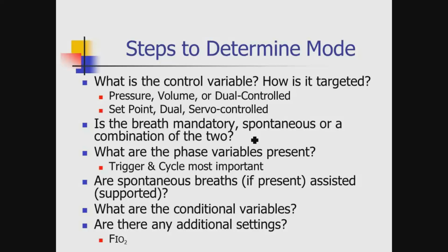Is the breath that is being delivered a mandatory breath, or does it have the ability to have spontaneous breath, or a combination of the two? Each mode is going to be a little bit different as far as whether or not they allow that. Those phase variables, what triggers, what cycles, what limits, what goes on during the expiratory phase, all of those we can quantify.